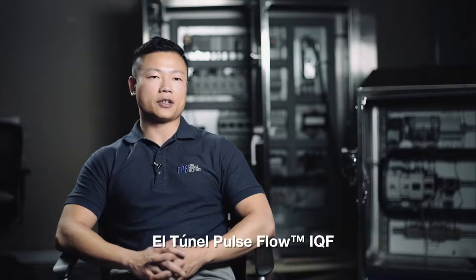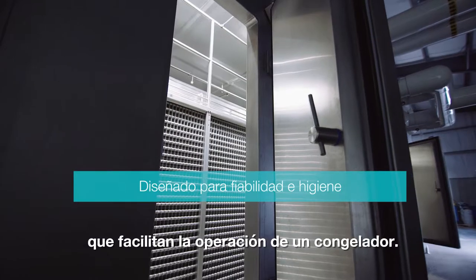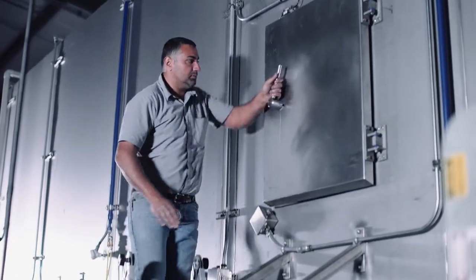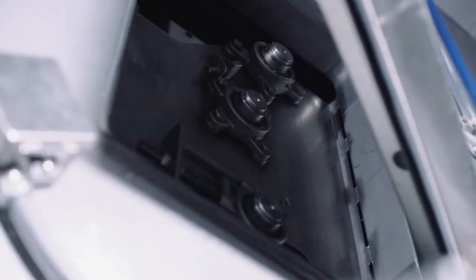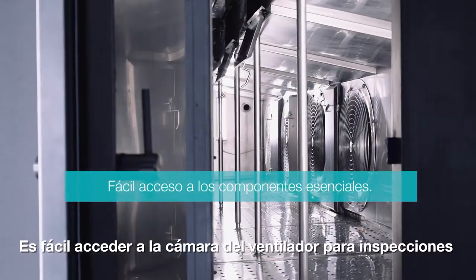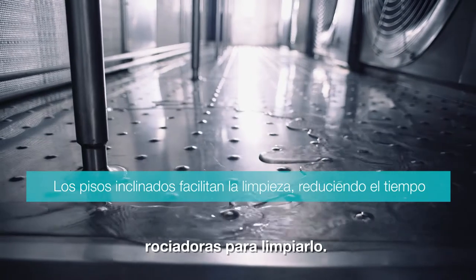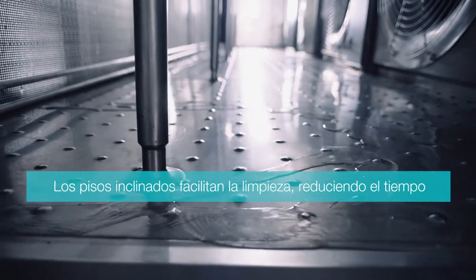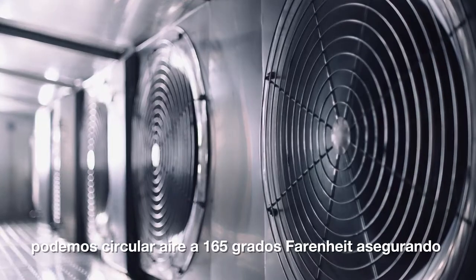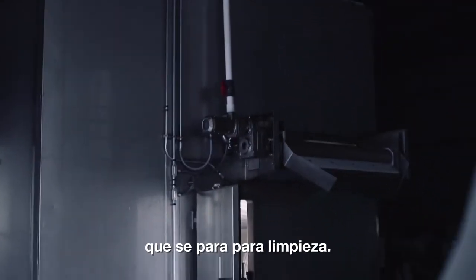The Pulse Flow IQF Tunnel exemplifies our commitment to hygiene in our drive to develop newer technologies that make operating a freezer much easier. The fan chamber is easily accessed for inspection, and if there are any hard-to-reach areas, we have a dedicated set of spray nozzles for cleaning those areas. With our CIP system, we are able to circulate 160 degrees Fahrenheit air to ensure kill step and refreshing of the freezer every time it's shut down for cleaning.